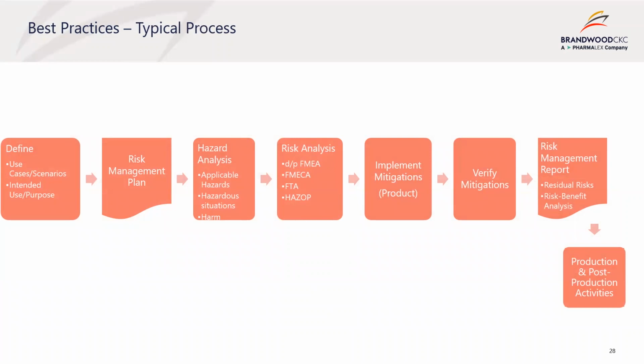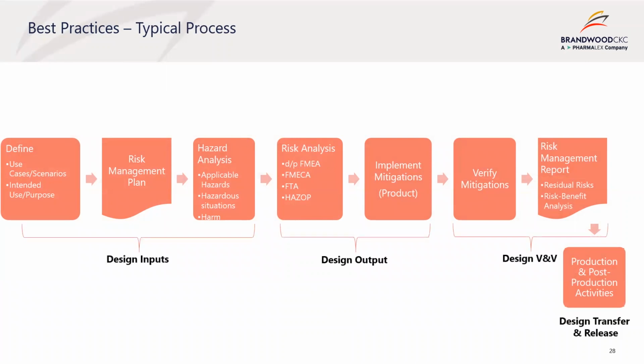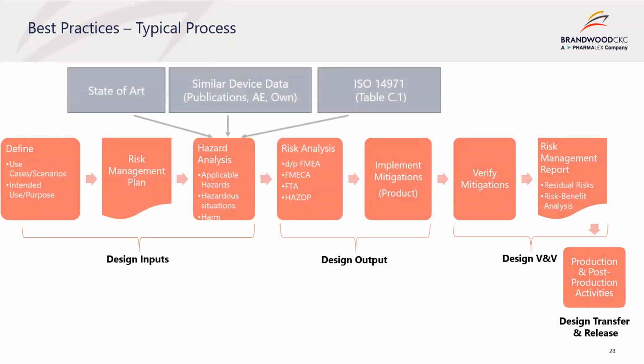Illustrated in this slide is a typical risk management process. I have now included how the activities may align with the design control processes of ISO 13485. Initially, during the design inputs phase, the process starts with defining the intended use, its characteristics, use cases, etc. The risk management plan is also established and the hazard analysis is conducted. The hazard analysis may include inputs from state-of-the-art, similar device data, or the list of typical hazards from Table C in ISO 14971. During the detailed design and design output phase, the risk analysis is conducted based on the identified hazards, and the required mitigations are fed into the various subsystems or system requirements.